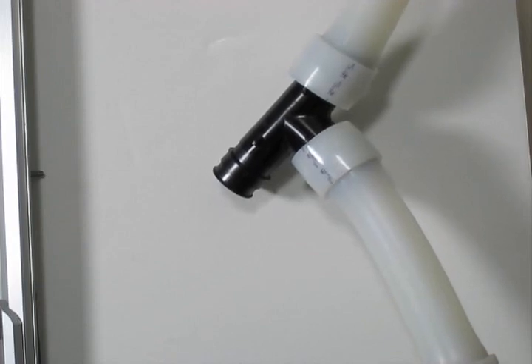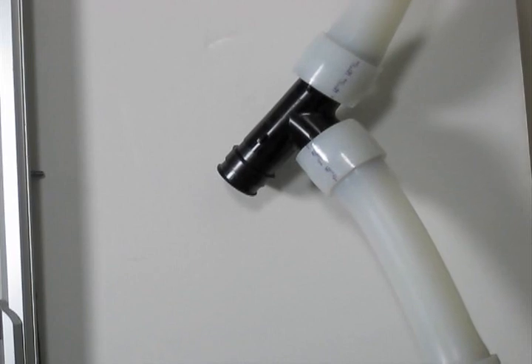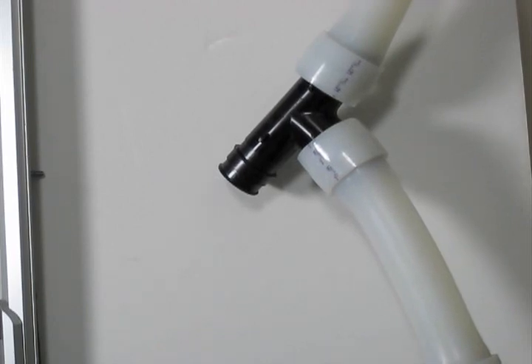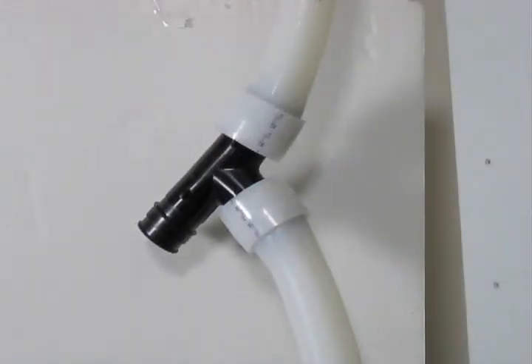To make a fitting, simply place a Propex ring on the end of the tubing, expand the tubing and ring with an expansion tool, and insert the fitting.